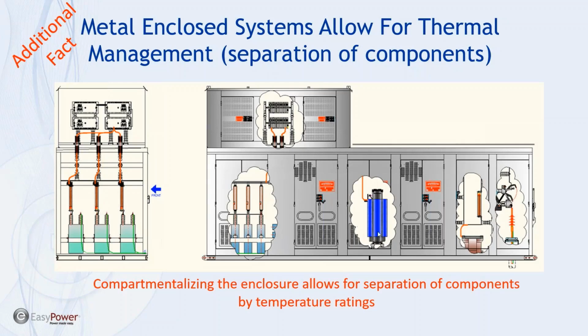We can separate the high temperature components, here the reactor, here the resistor, into their own compartments, and allow those compartments to run hotter because that's where the losses are. And then we can put capacitors in their own compartment and run those at lower temperatures. So these components are low loss components. Put a fan in here. It does not take a whole lot of effort to keep the temperature of those capacitors within their rating.